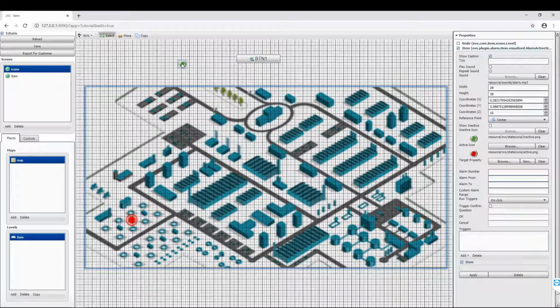The first setting is the title of the button. Create a logical name for every NVX element. The checkbox below is used to define a sound to be played at power up. The settings below refer to the size and position of the button. Here you can also specify the X and Y coordinates manually so that the symbols are on the same line side by side. By activating the Show Inactive Icon checkbox, the button is also displayed when the alarm is not active. When the alarm icon is unchecked, the alarm is only displayed when it's active.